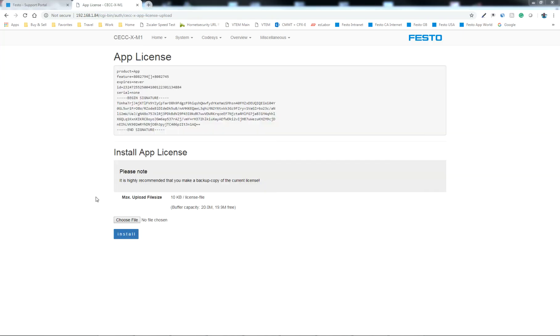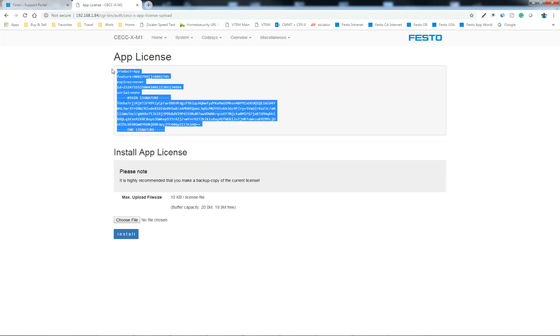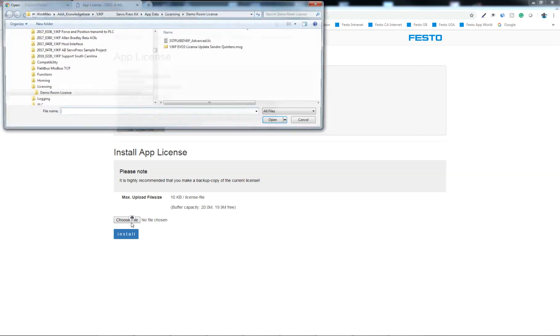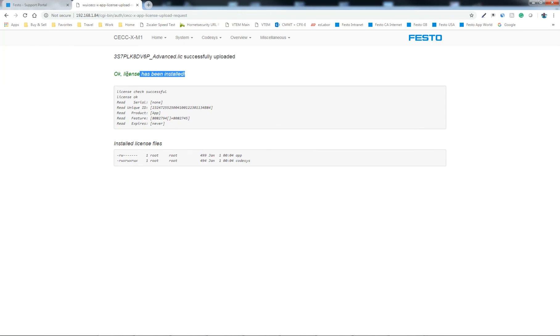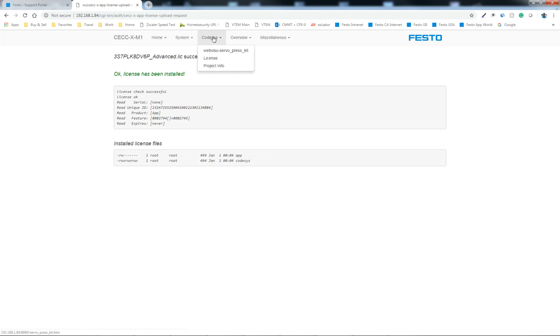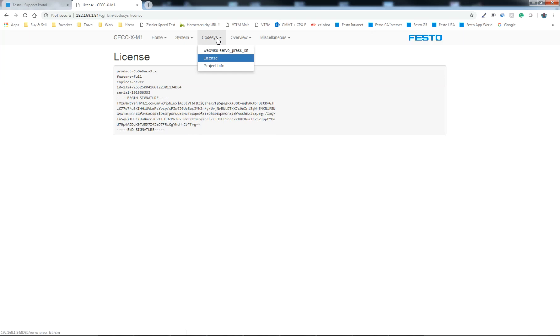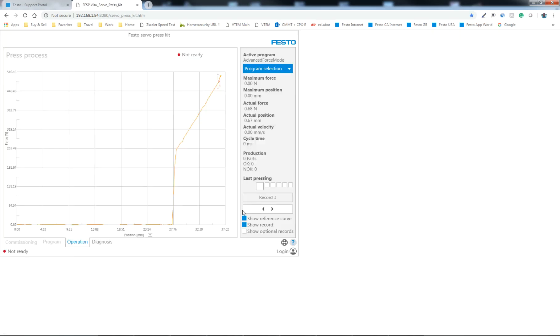I've done this procedure over again. And, now I have the proper app license. Again, if I was to install this and say install. It says, okay, license has been installed. Everything is all good. Serial number is all good. Everything is a match. So, again, recap. Replacing PLC, you need a new license. And, that's how it works. And, I can go to the license overview here. And, I can see that I have a license. And, now when I go to my web visualization, I don't have this thing right here. So, we have now updated program, application, firmware, license, everything.